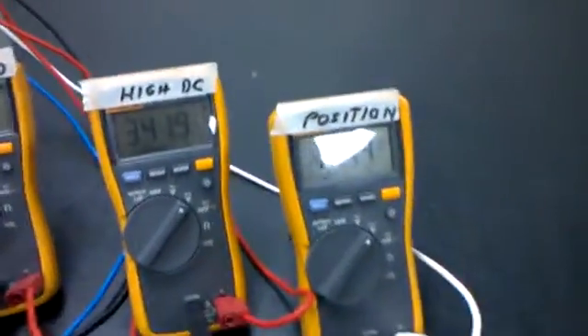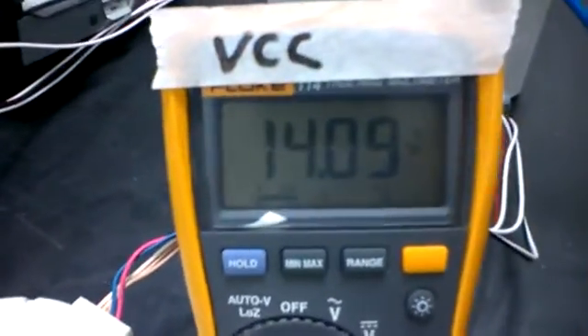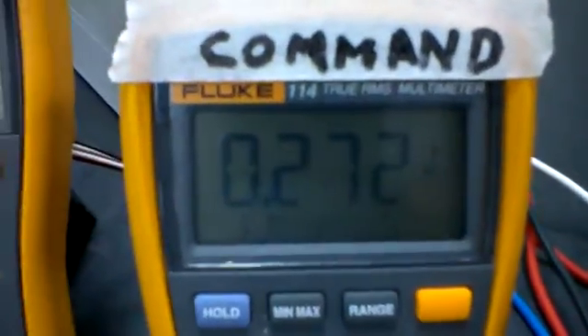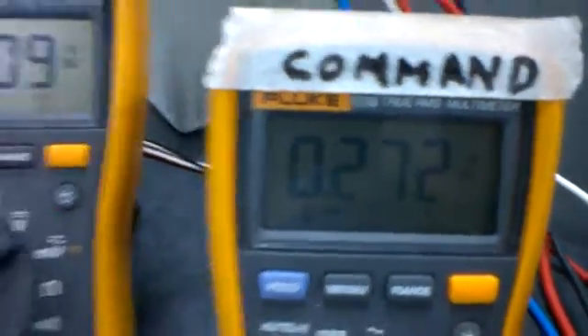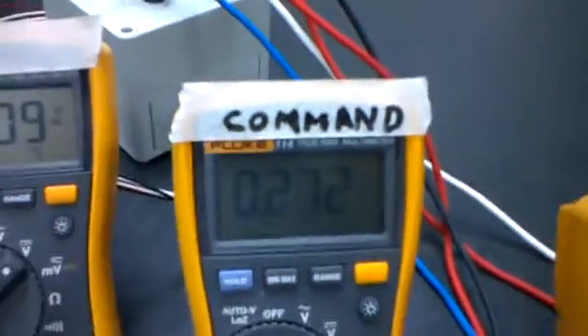Okay now, before you begin, the most important test is that you don't have this unit turned on other than the power supply. And what we're really looking for is this. We want to make sure that we've got a control voltage being sent out. Now if the board puts that out, the board's good. The command voltage here hasn't really begun yet. We're sitting on a residual 0.2 of a volt. Here we can see that we've got our power.